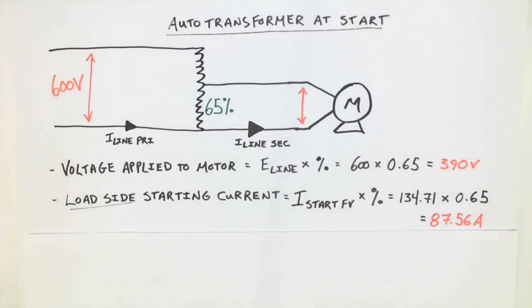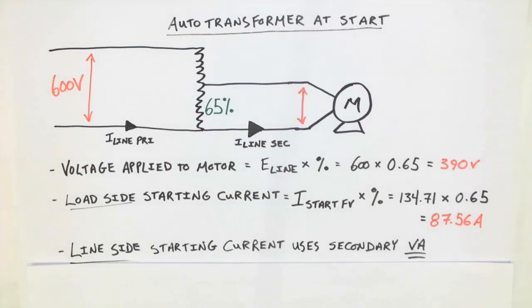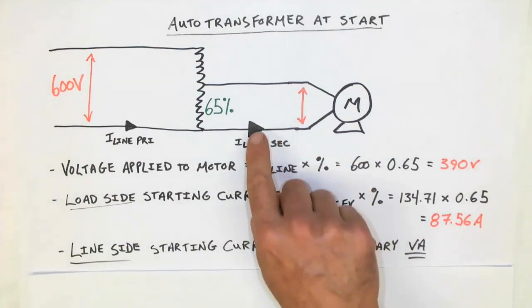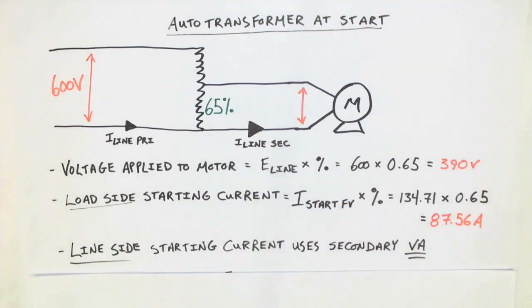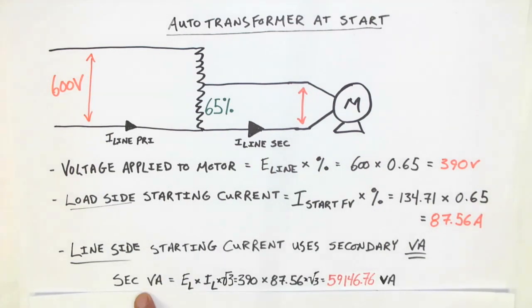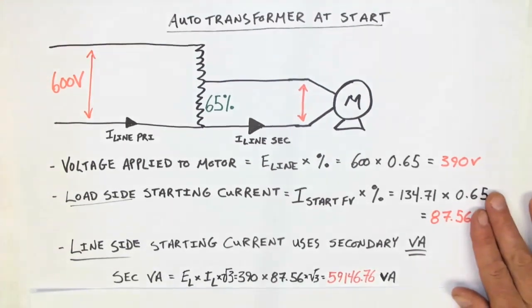The line side is a little bit different. The line side starting current uses the secondary VA as a starting point for the calculation. So we need to know what the secondary VA is because VA in equals VA out. VA in would be over here, VA out is over there. We're first going to calculate the secondary, or VA out, of this autotransformer section. To do this, we're going to take E line, I line, and root 3, our basic three-phase calculation. 390 times 87.56 times root 3 gives me the total three-phase VA of 59,146.76. This is the total VA that the motor is currently using. And we're going to use this in our transformer in order to calculate the primary value.